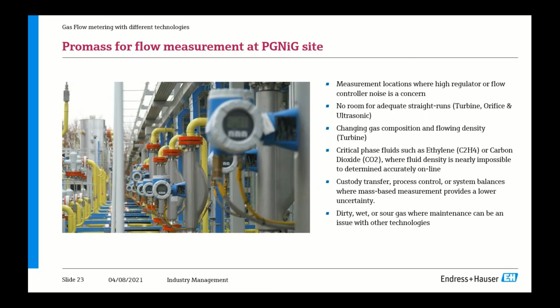As mentioned before, in this application, vibrations are very common as well. As previously commented, Coriolis is very robust in these types of applications and is not affected by that. And because Coriolis meters don't measure velocity, flow conditioners are not required. This even further reduces the cost and complexity of the installations and allows you to install the meter where it is more convenient.